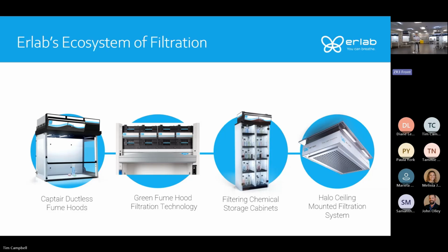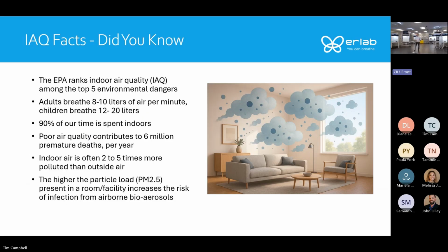So this adds equivalent filtered air changes to a space, installed similar to a light, and you can add carbon filtration for chemical vapors and odors, or HEPA filtration for particulates to improve the overall indoor air quality in the space. Now I'm going to touch on indoor air quality.